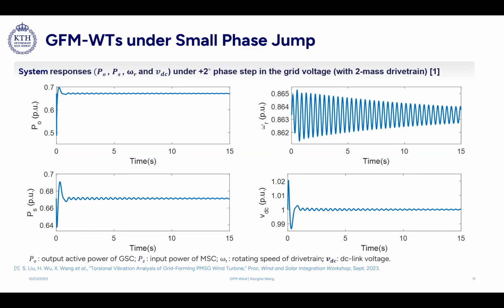on the turbine shaft. Here, just to show you some basic studies of what we did with DNV and Shell, you can see that for a small phase jump of 2 degrees in the grid voltage, the speed of the drivetrain is oscillating. But of course, this is based on the standard drivetrain model. We can optimize the drivetrain, and also its damping, using some mechanical improvements. Here, I just want to convey a message. Whenever we talk about a nearly constant voltage source, that is at the cost of the energy source limit. We cannot just randomly say we can maintain it as a voltage source.